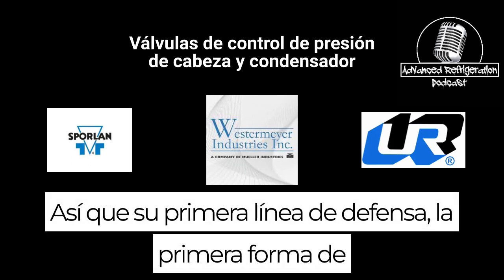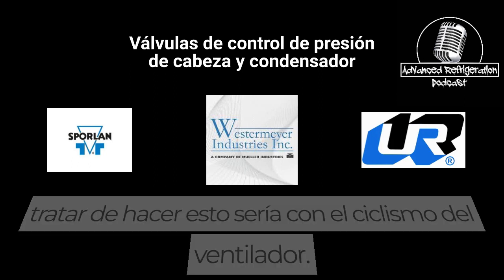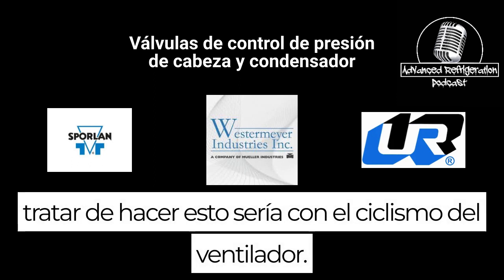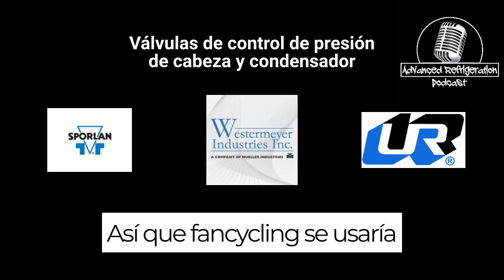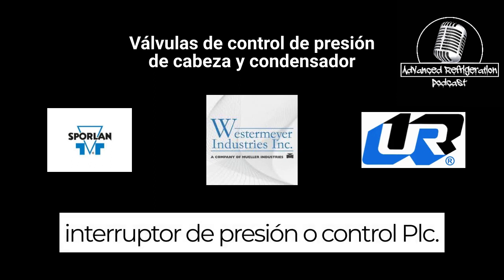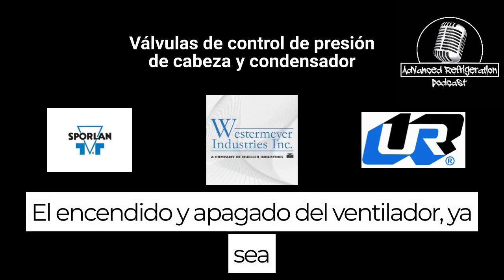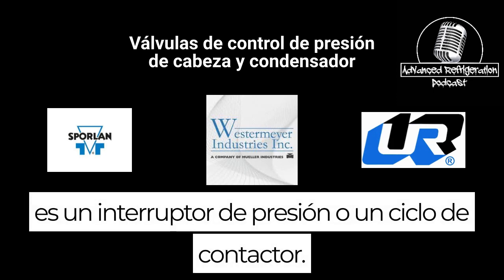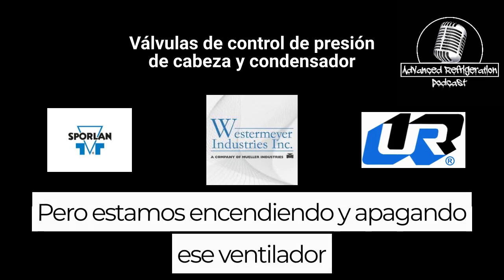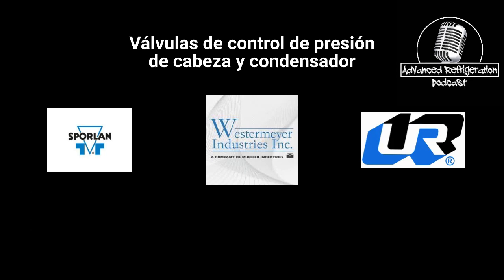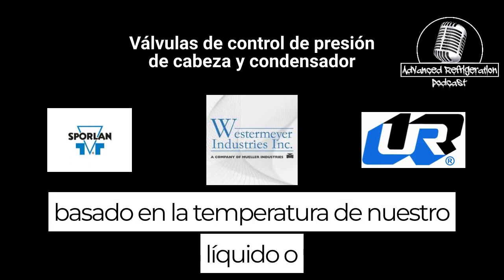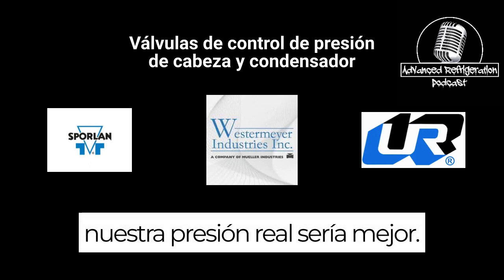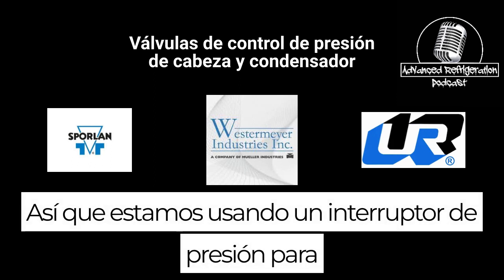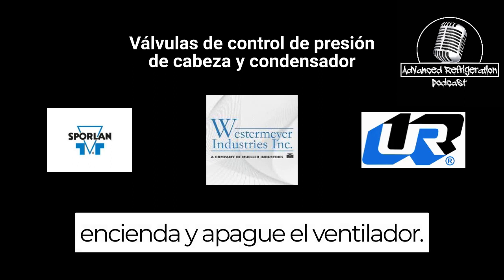So the first line of defense, the first way to try to do this, would be with fan cycling. Fan cycling would be used with a pressure switch or PLC control, the fan turning on and off, whether it's off a pressure switch or contactor cycling. We're turning that fan on and off based on either the temperature of our liquid or our actual pressure, which would be better. So we're using a pressure switch to cycle the fan on and off.